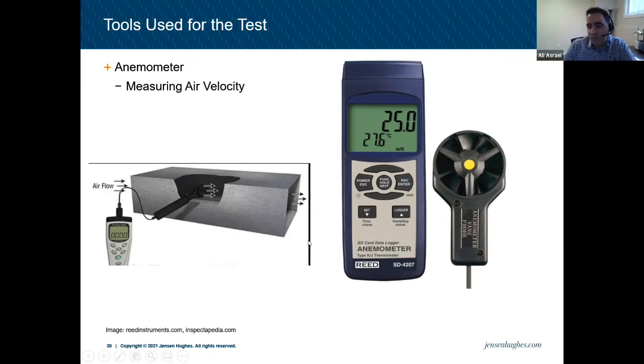Basically, sometimes there is a hatch in the duct, so you can open it and put this inside, and when the air flows, this thing keeps turning and gives you a number that you can use to understand the air velocity. Or if it's not available, you can do it at the very end here or here, even at the intake or here. So it depends what is available. A proper way is if a hatch is available, you open it and put this inside the duct, right? But it's not all the time something that you can do, because sometimes there's a shaft built around it, and there's no access technically to it.